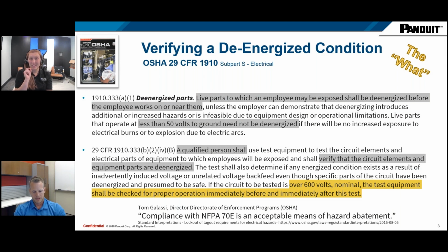I've seen people do the live dead live check and try to do phase to phase and phase to ground. They were giving it their best shot, but the connection points had those silly little touch safeguards. They're not silly, they're great. They're helpful for incidental contact, but it made their leads not actually reach all the way in and make contact. Yeah. And I was like, all right, you're going to need different leads or you have to take the cover off. And they didn't even think about the fact that their leads weren't making contact. So yes, even if you do all the steps right, there is still a chance of missing something.